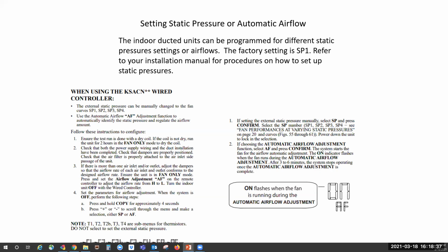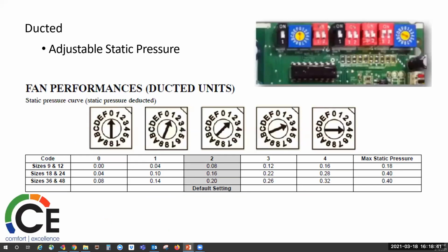On the 36,000 BTU and above, you will use these little dials, and they're always set for default of 2, but with 4 being the highest. So if you have to adjust your static pressure on these, it is crucial that you do that.